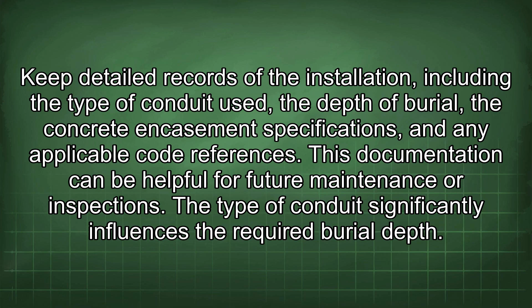The type of conduit significantly influences the required burial depth. Rigid metal conduit, or RMC, and intermediate metal conduit, or IMC, are generally stronger and can withstand greater external forces compared to non-metallic conduits such as PVC. As a result, RMC and IMC may be allowed shallower burial depths in some situations.